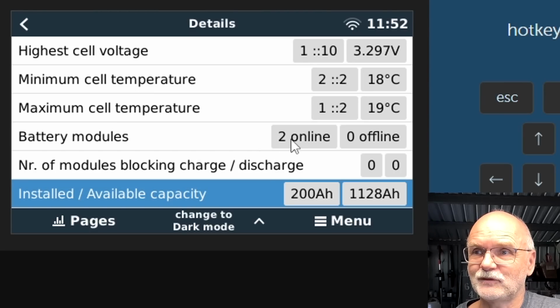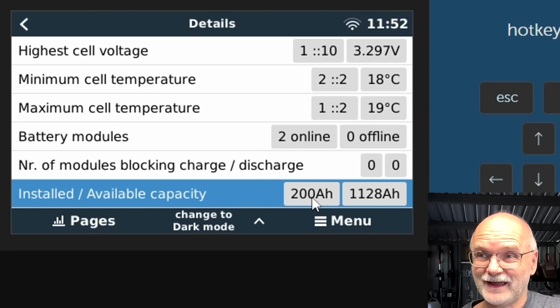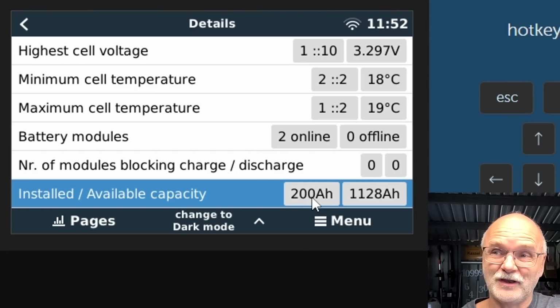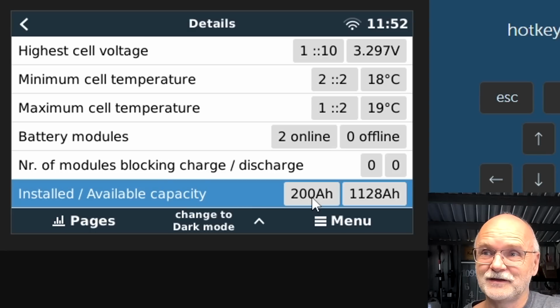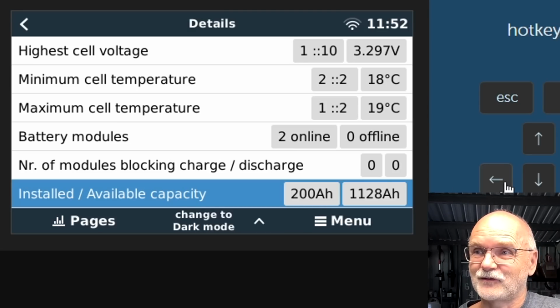Here we've got 2 batteries online, 200 ampere hours, which is not correct because the slave battery has 230 and the master has 100. But it only sees 2 batteries online and doubles the capacity, which is totally wrong. So that is a big bug in the software.